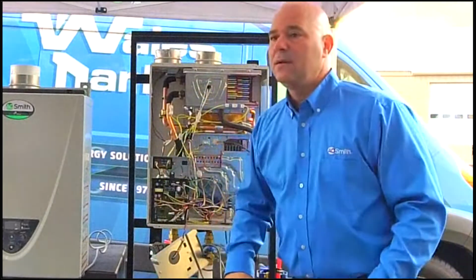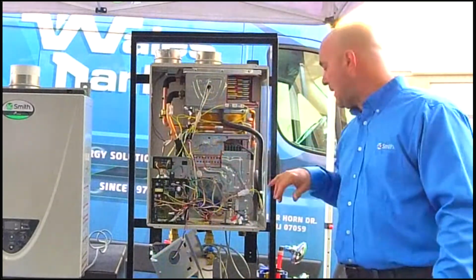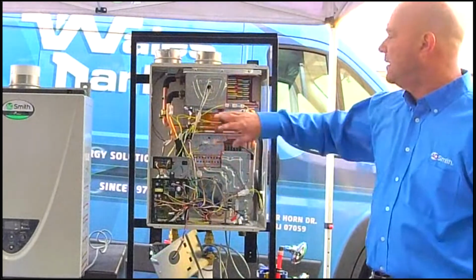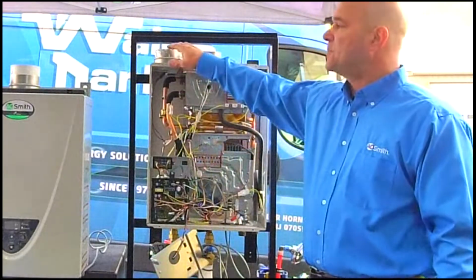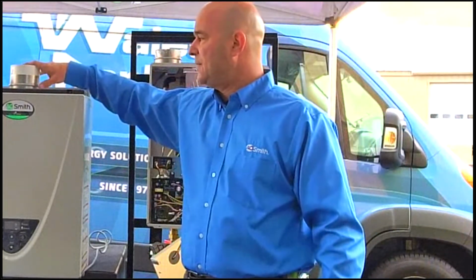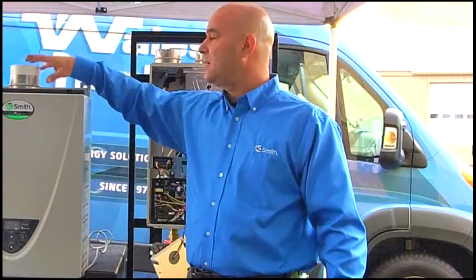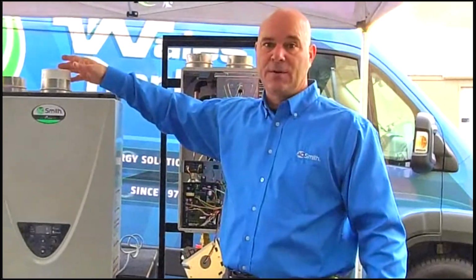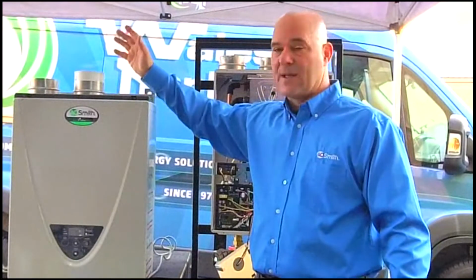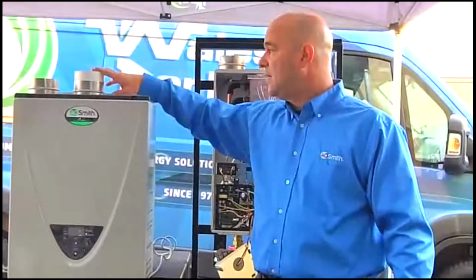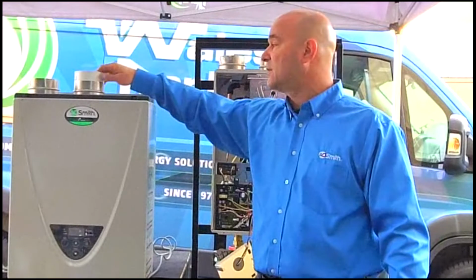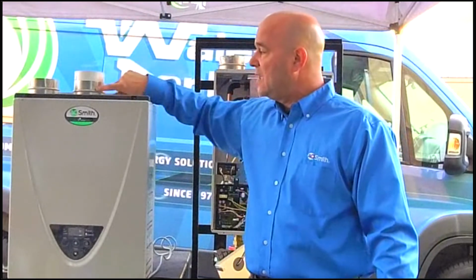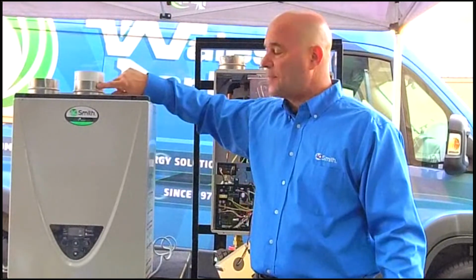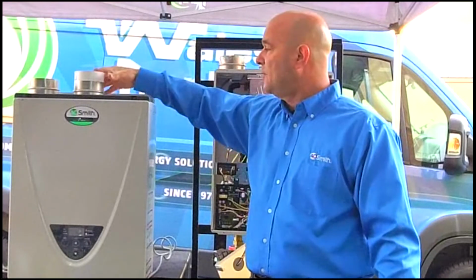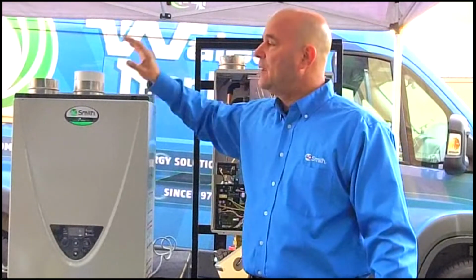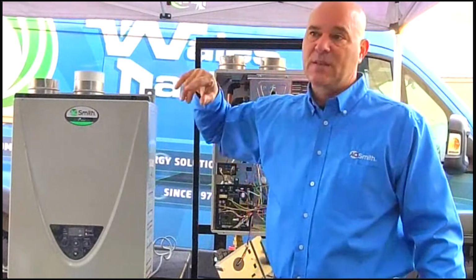That is on the yellow wire. That's the safety side. Again, on the trap, we have it on the trap. That is our sensor. 3-inch PVC couplings come with this unit. The 3-inch PVC coupling tucks down inside if you're going to use PVC. Again, there's a resin shortage right now in the US, so PVC may not be your best venting option. Polypro is a good option. You get the Polypro adapter. Boom, Centrotherm adapter slides right in. Vent it out with Centrotherm.